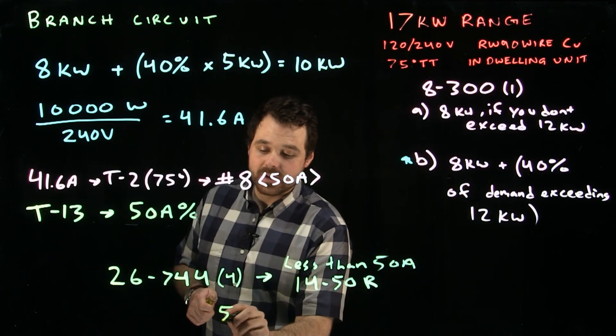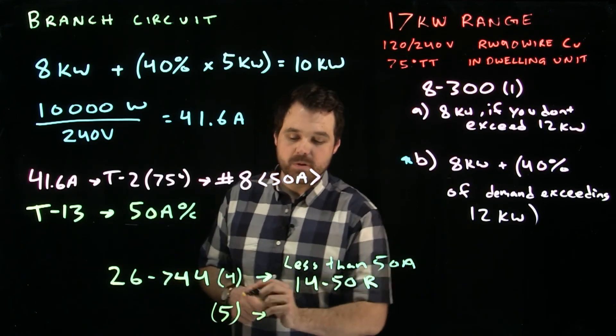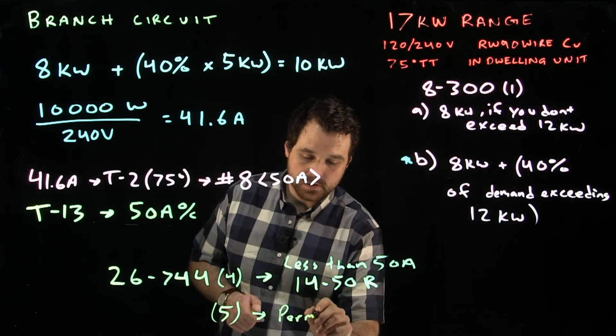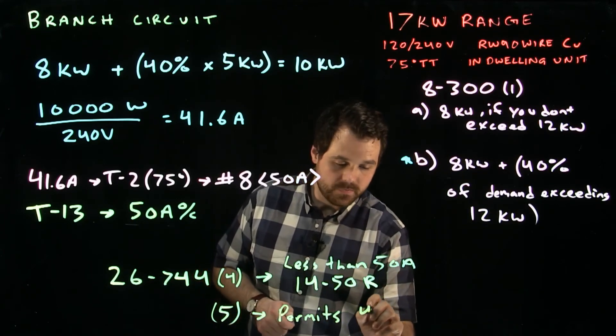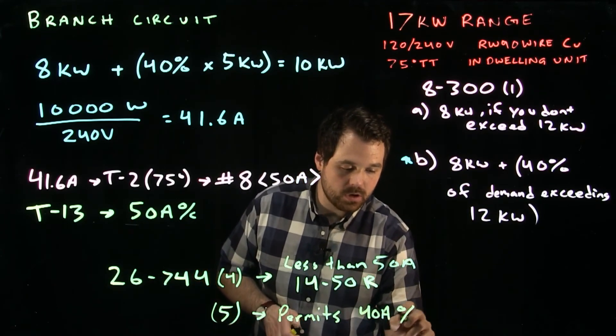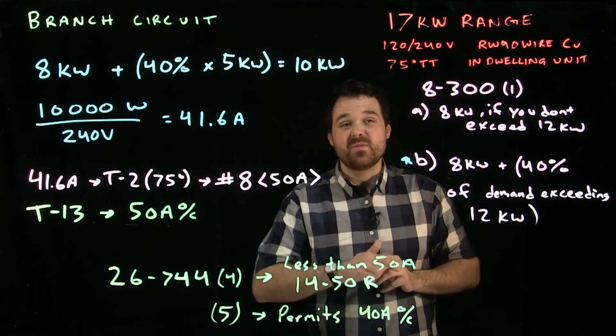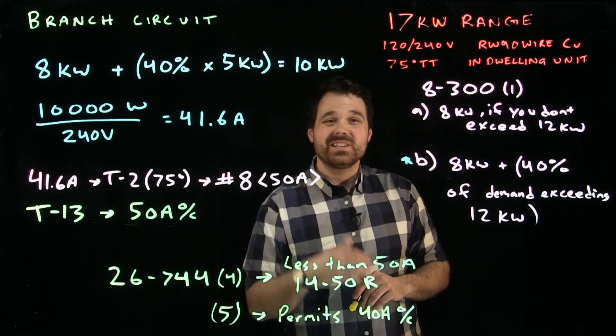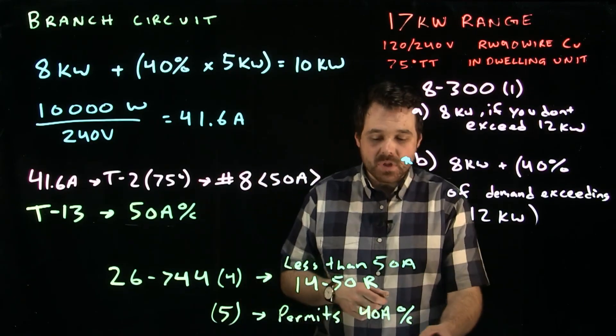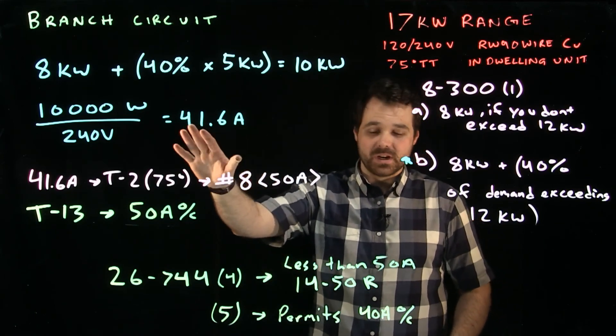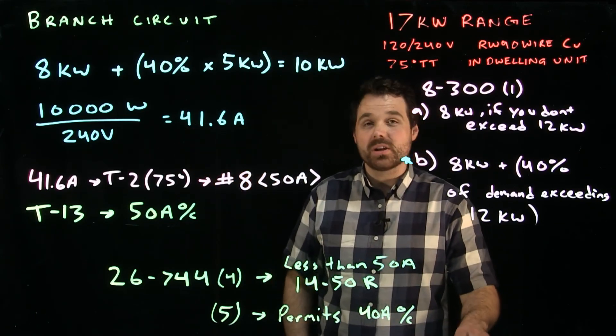Sub-rule 5 does permit you a 40 amp overcurrent device. It does allow you to put a 40 amp overcurrent device, but you would still need that 50 amp wire. In this case, we wouldn't go with the 40 amp overcurrent device because that's not big enough. We would go with a 50 amp in our case here.